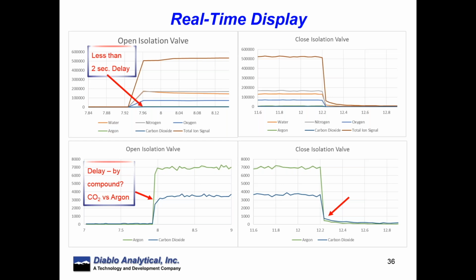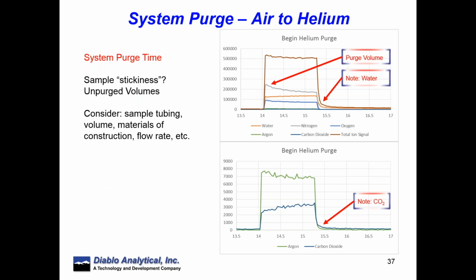So for example, we can look at syngas and we can look at combustion gases, but for quantification, water tends to get stuck and buffered essentially in the interface. So you can see that CO2, in the bottom right example, has a very slight delay to return over argon. And so that is slightly more sticky than, say, everything else. And so that shows the water curve coming down in the top, and then the CO2 curve versus argon coming down. Again, the point of this is showing how quickly it responds to a change in sample composition, or switching from the gas at the front end of the process to the product end, or switching to a calibration cylinder.